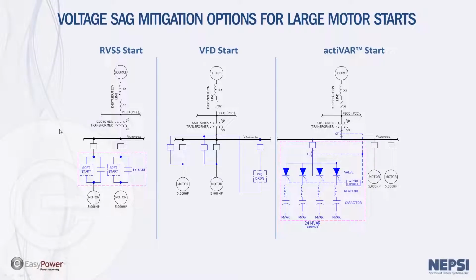The issue with the reduced voltage soft start is that it operates by reducing voltage to the motor. It's basically like a light dimmer. As you try to push the voltage further and further down to reduce inrush current, there becomes a break point where the motor will not start, and the system will still have a voltage sag that exceeds the utility limit. And in such cases, the design engineer is required to look at a VFD starter.